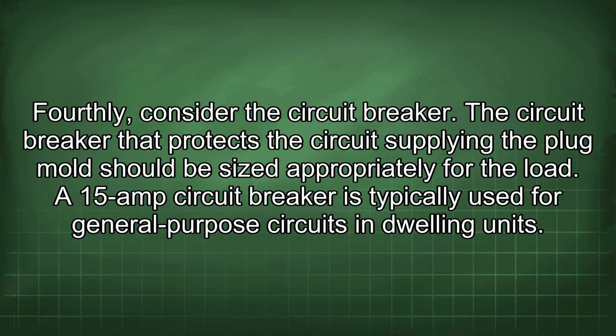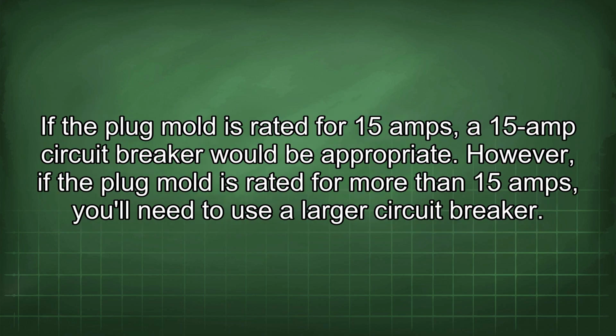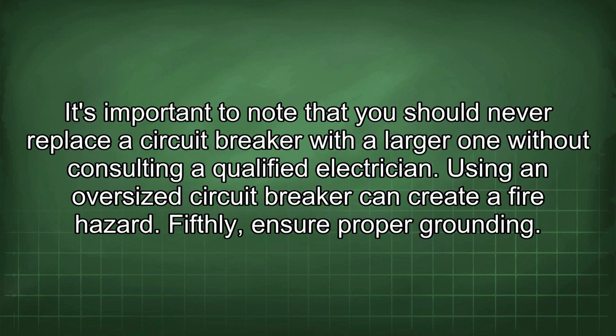Fourthly, consider the circuit breaker. The circuit breaker that protects the circuit supplying the plug mold should be sized appropriately for the load. A 15 amp circuit breaker is typically used for general purpose circuits in dwelling units. If the plug mold is rated for 15 amps, a 15 amp circuit breaker would be appropriate. However, if the plug mold is rated for more than 15 amps, you'll need to use a larger circuit breaker. It's important to note that you should never replace a circuit breaker with a larger one without consulting a qualified electrician. Using an oversized circuit breaker can create a fire hazard.